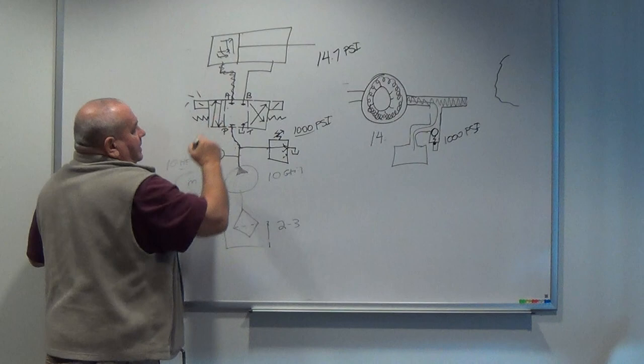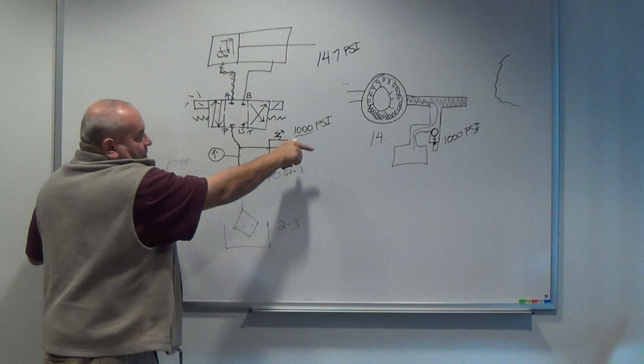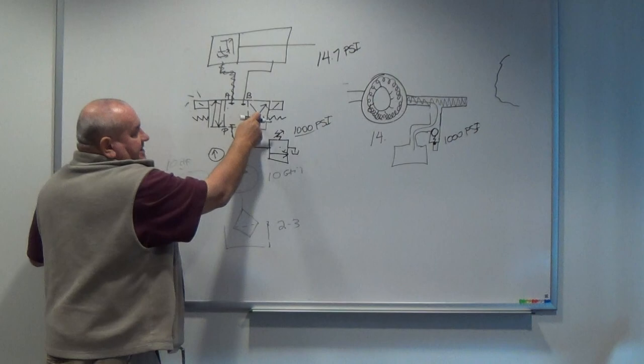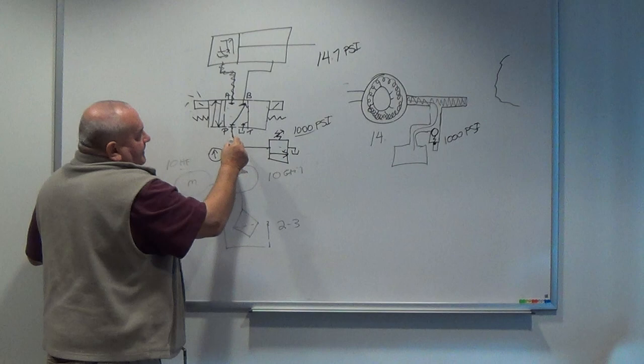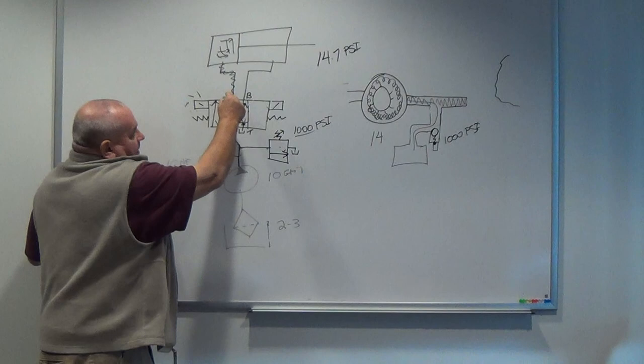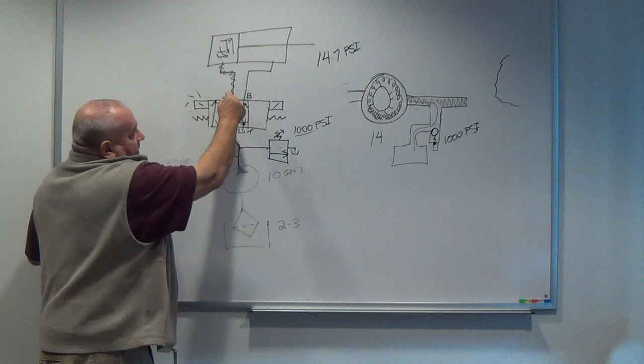I'm now in my neutral condition. So therefore, this is going to stay open and dump the tank. If I look at it this way, that I activate this side of my directional control valve, then this flow path comes in. And you can see my crossover. My oil comes from my pump in through my crossover, up through here, and it now brings the rod back, right? The oil on this side is going to cross over this way and it now returns the tank.